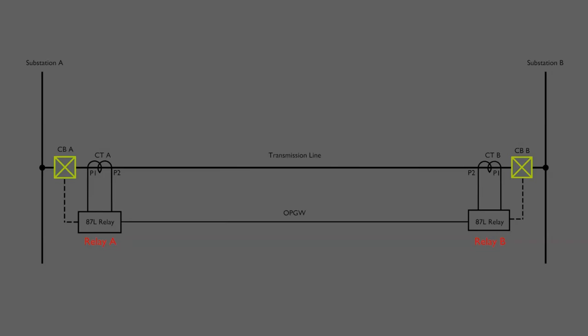Now we shall discuss how the currents are compared in the relay. It is obvious that there will be a small time delay between receiving and sending the current signals. Consider relay A: the current signal from CTA will reach the relay much faster than the signal from CTB, because for the CTB current signal it is converted and reconverted. Due to this conversion, propagation through the communication OPGW, and then reconversion, the signal from the far end will arrive with a delay, making accurate comparison of current signals from both CTs difficult.